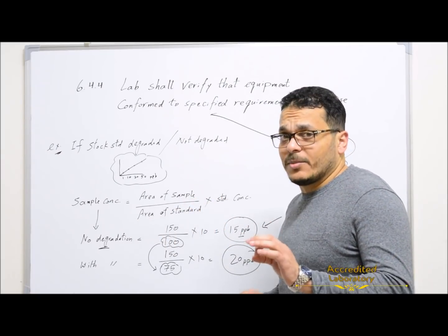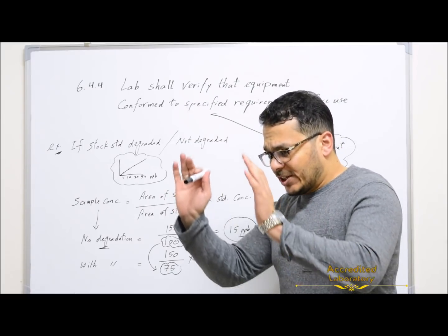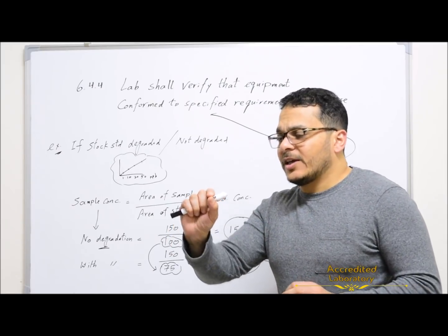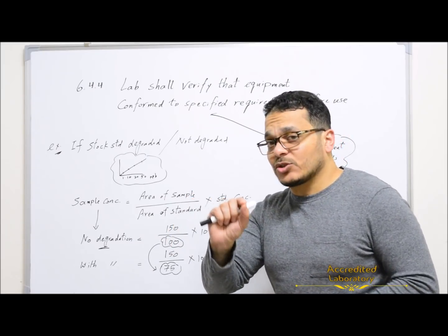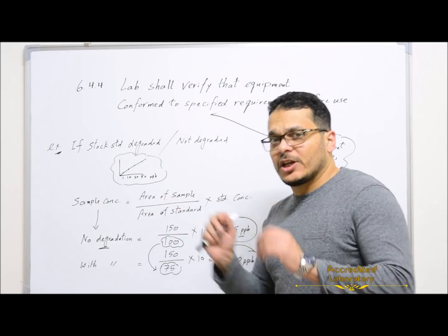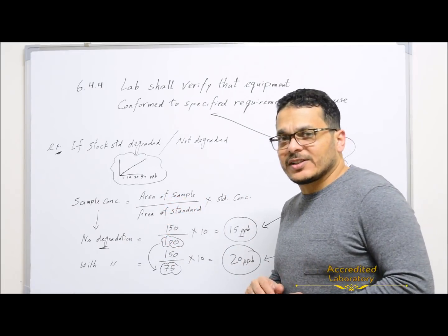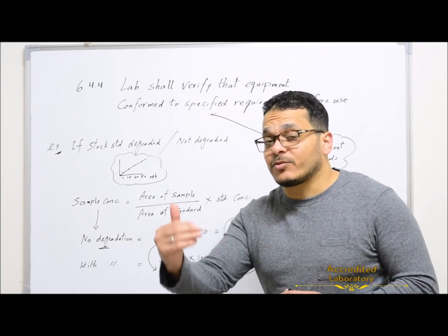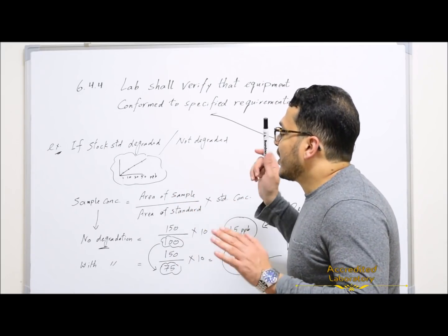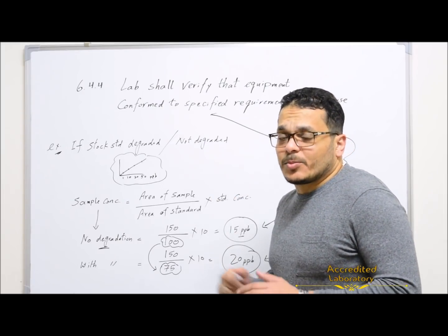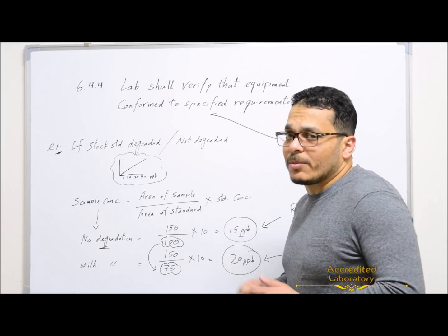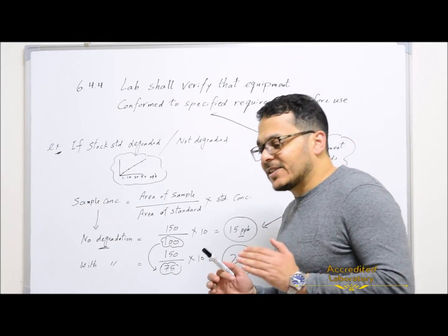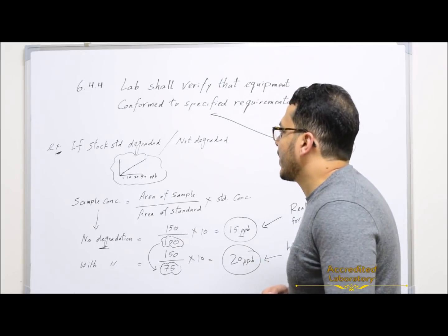Only from CRM, if you get a result in the range that they gave you in the certificate, then your standards are not degraded. Your standards can be extended for another 1 year. But if you analyze a spike sample or your samples using this standard only, you cannot decide if this standard can be extended or not.